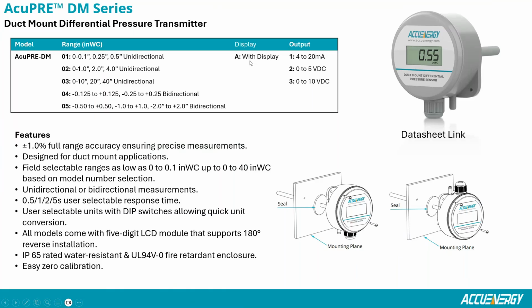Right now, the duct mount unit comes only with display. Basically, this is a placeholder. Eventually, there's going to be one without display, and then what analog output you require: 4-20, 0 to 5, 0 to 10. The LCD display is nice for the installer, for making sure obviously the inches of water column or pascals matches what the front end is displaying, and make sure you have the sensor or the front end configured correctly, and then basic troubleshooting. Right now, all the pressure products are plus or minus 1% full scale accuracy.